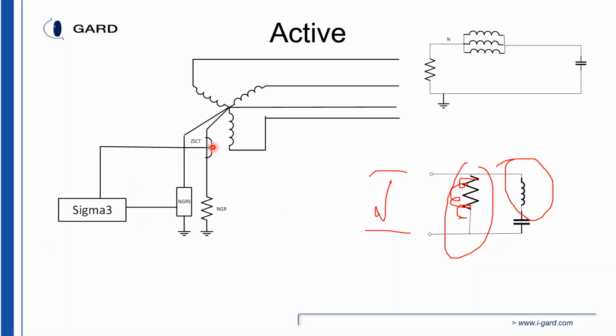The Sigma relay, zero sequence CT, you need the NGRS to normalize the voltage and use this in passive mode. There's also an NGRX, and we're making the determination of whether to make that one package or two packages, but the NGRX is used to inject the signal onto the system and measure the integrity of the resistor.